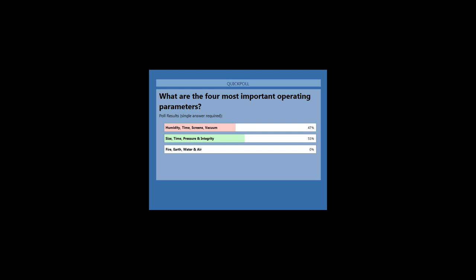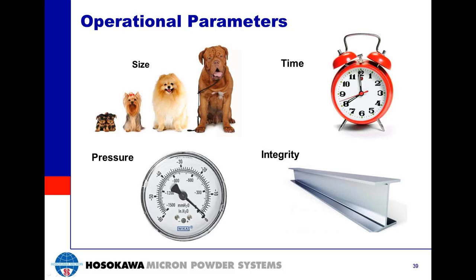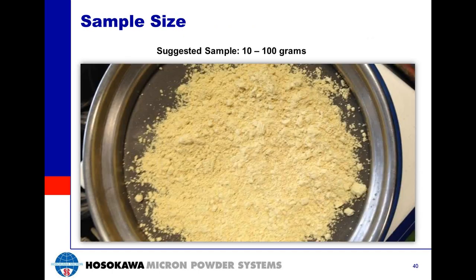The four operational parameters for accurate, reliable sieving analysis are: sample size, sieving time, sieving pressure, and sieve screen integrity. For sample size, when producing repeatable results, use the same sample size for each analysis. On the Hosokawa Micro Airjet Sieve, we suggest sample sizes anywhere from 10 to 100 grams per cycle, product dependent. If your product is lighter in density, use a smaller sample size around 10 grams; if heavier in density, use a larger sample size.